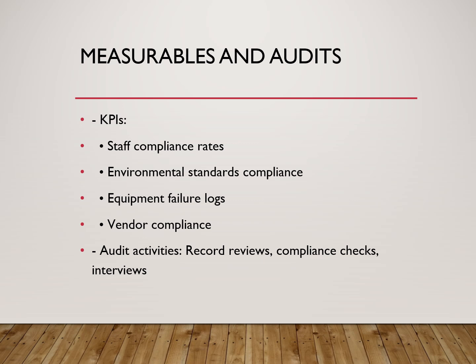The 4 audit killers that expose labs. The first is the we do it but don't record it fallacy. In a lab, staff performed daily freezer checks but never logged them. During an audit, the assessor found vaccines spoiled with no proof of monitoring. What is the ISO 15189 rule? No record equals never happened.